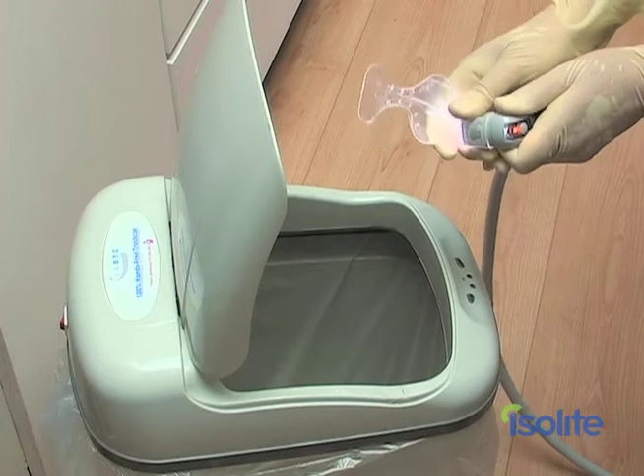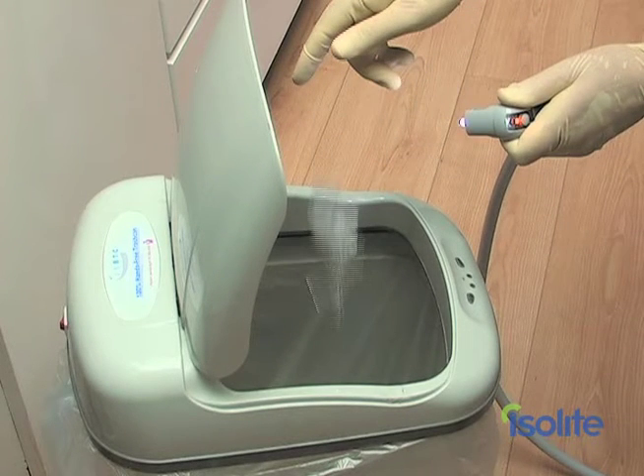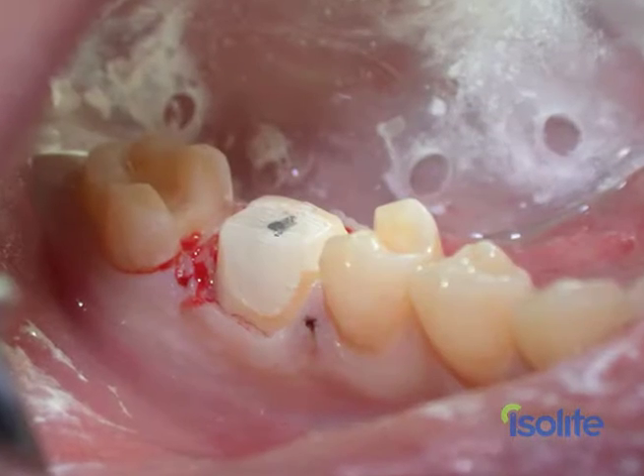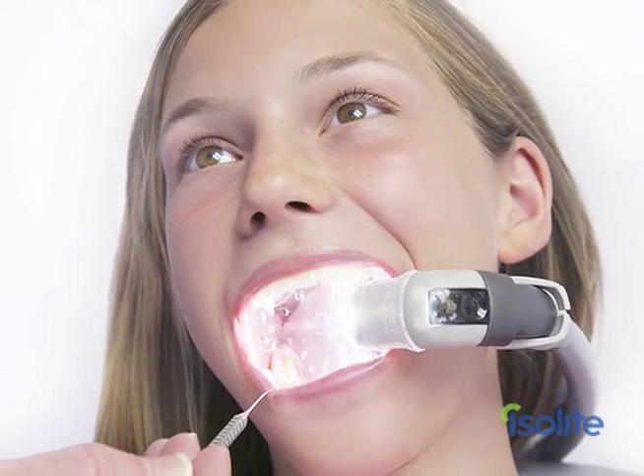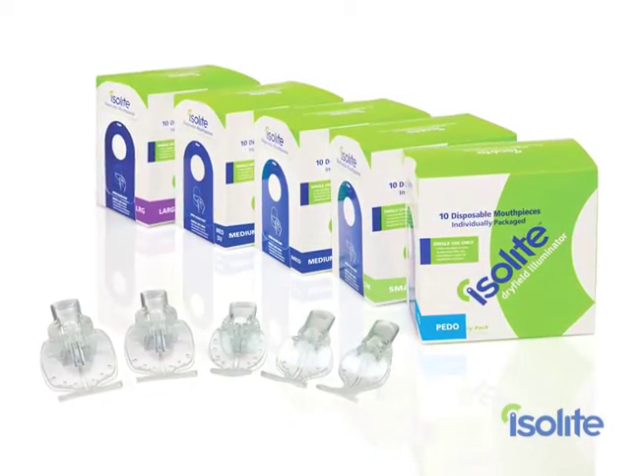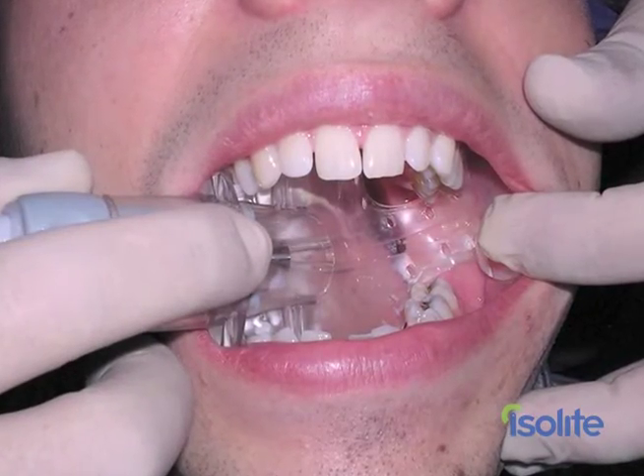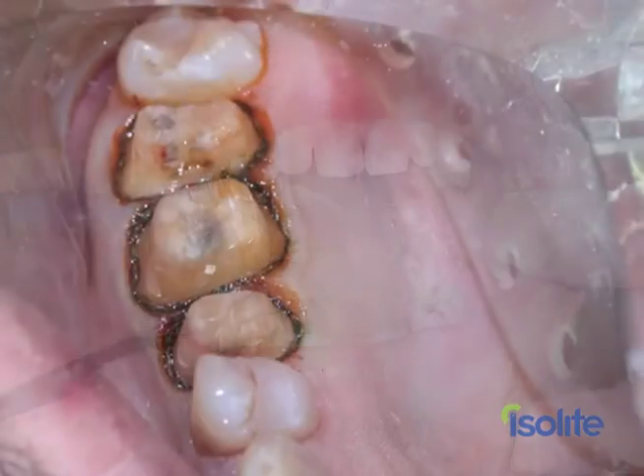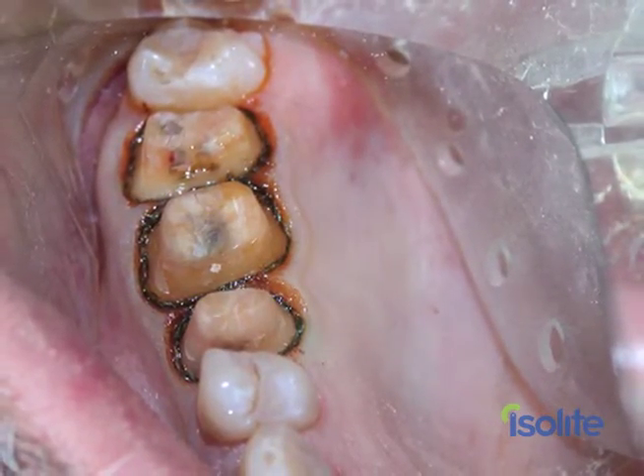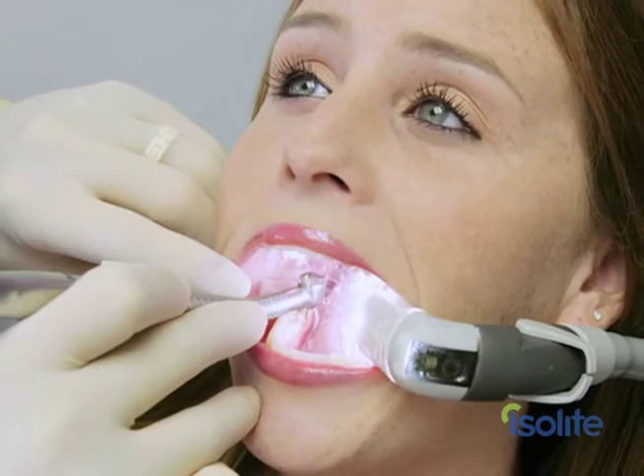The first step in cleaning your Isolite dry-field illuminator, or IsoDry, is to remove the single-use mouthpiece from the control head and safely dispose of it. To eliminate the risk of patient cross-contamination, Isolite mouthpieces are for single-use only. Never attempt to sterilize an Isolite mouthpiece. Microfissures in Isoflex polymer will trap bacteria and can result in the transmission of infectious pathogens. Remember, disposable means safe.